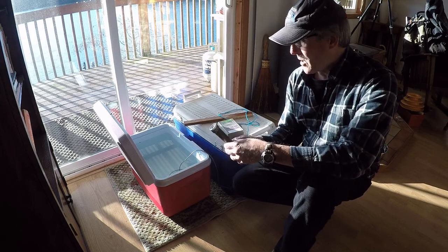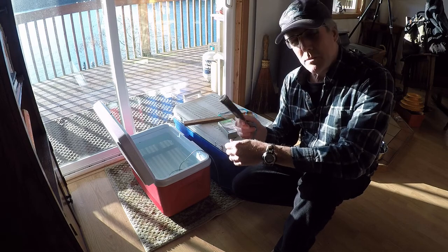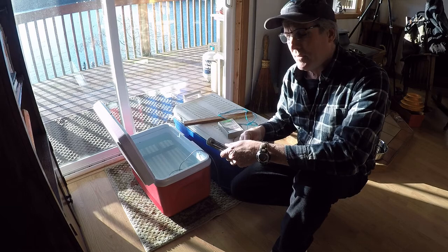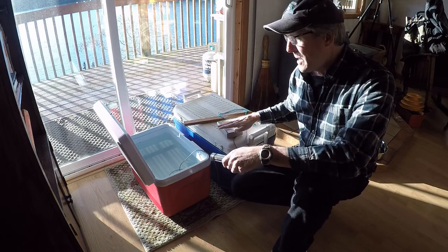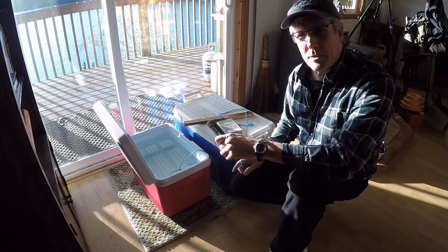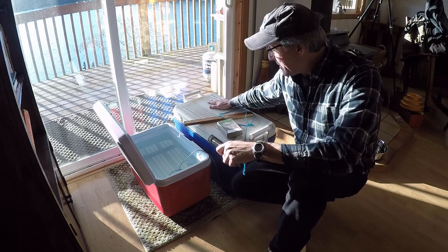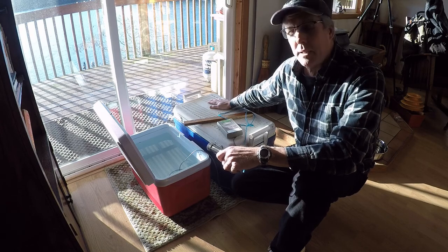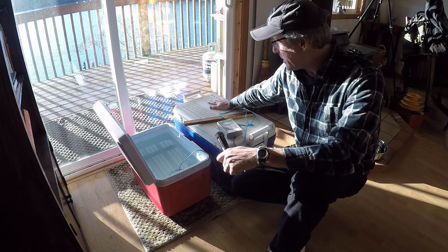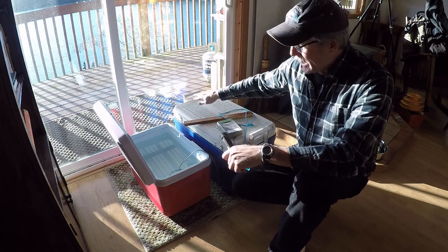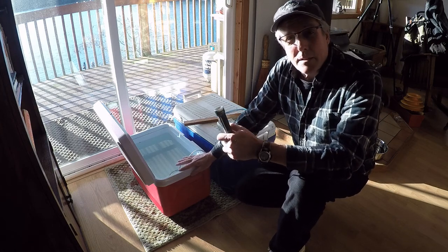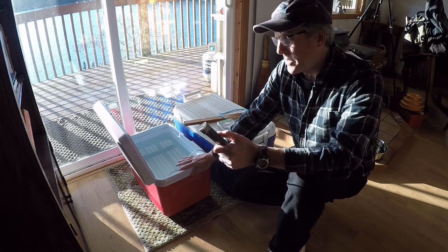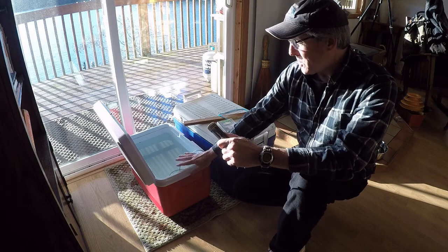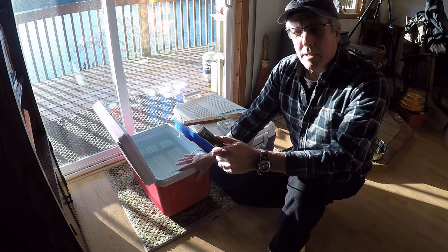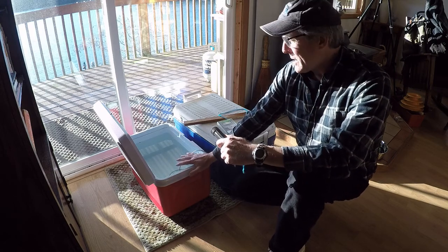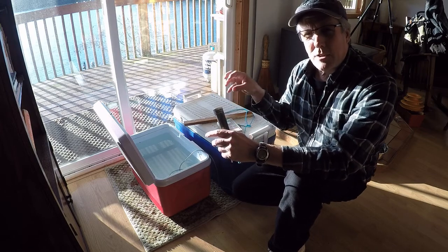So our goal here is to make sure that the continuous temperature probe is reading the same temperatures that the NIST thermometer is reading. To do that, we're going to put it in 2 different temperature water baths. We've got a bucket or a cooler full of ice water here, so that'll of course be down around 0 to 1 degrees, somewhere in there, for our low temperature. And then for our high temperature, we want something that's above 18 degrees. So 18 degrees is that sort of magic number for a lot of the cell-mounted rearing safety zone. So we want it to be at least that, and they recommend usually having it around 25 degrees. So kind of room temperature water. That'll bracket the zone where all of our data that we collect should be between those 2 points.